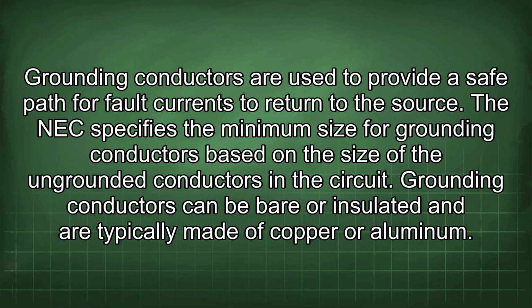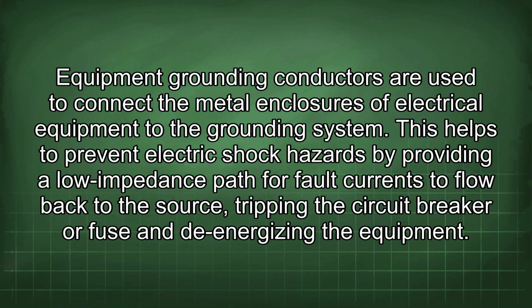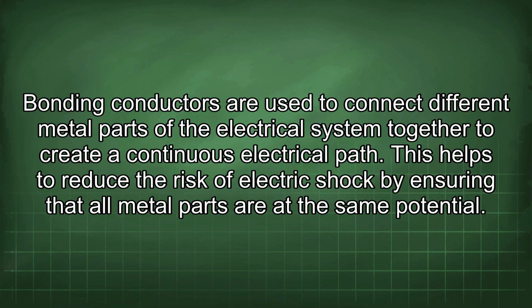Grounding conductors are used to provide a safe path for fault currents to return to the source. The NEC specifies the minimum size for grounding conductors based on the size of the ungrounded conductors in the circuit. Grounding conductors can be bare or insulated and are typically made of copper or aluminum. Equipment grounding conductors are used to connect the metal enclosures of electrical equipment to the grounding system. This helps to prevent electric shock hazards by providing a low impedance path for fault currents to flow back to the source, tripping the circuit breaker or fuse and de-energizing the equipment. Bonding conductors are used to connect different metal parts of the electrical system together to create a continuous electrical path. This helps to reduce the risk of electric shock by ensuring that all metal parts are at the same potential.